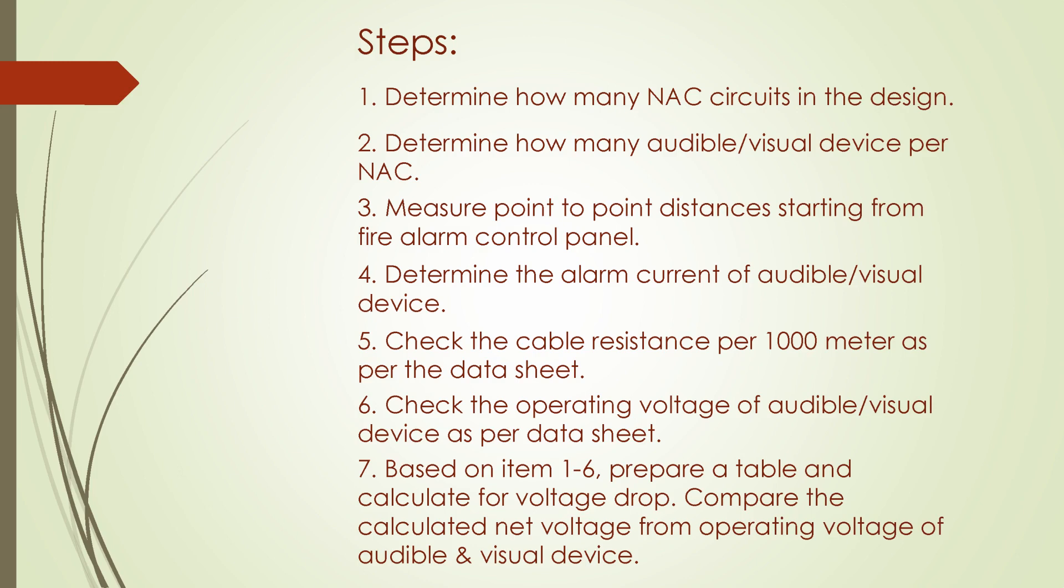Fourth, determine the alarm current of audible and visual device. Fifth, check the cable resistance for 1000 meter as per the data sheet.